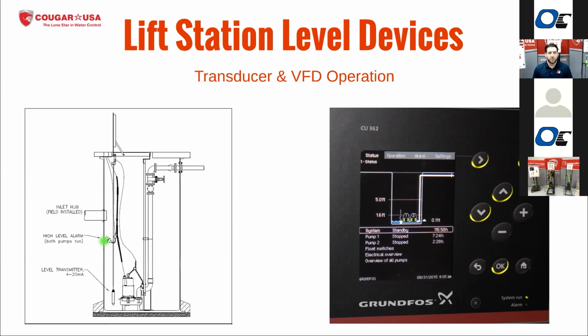So that high level float switch there is a backup float switch, so that if our volume in the tank gets up to that, we will get an alarm that we have a sensor fault, and it'll turn on both pumps and run them till that float switch goes down. So it will cycle the pumps based on that float switch as a backup, and every time they cycle, you're going to get that alarm.